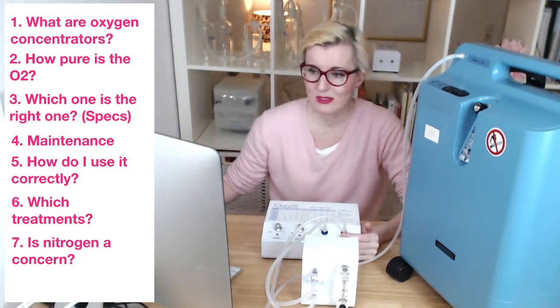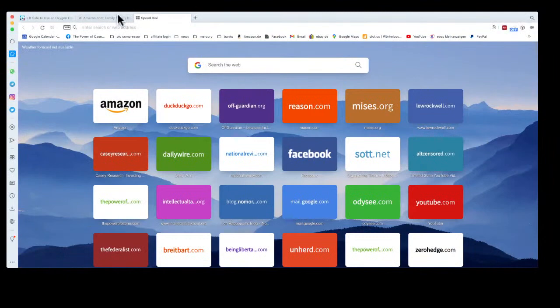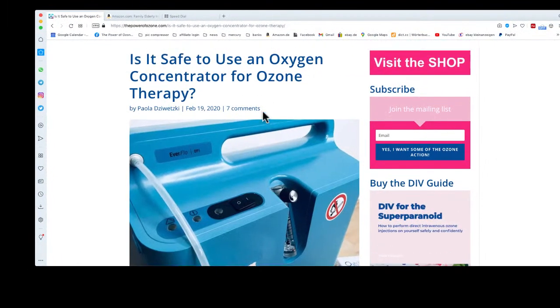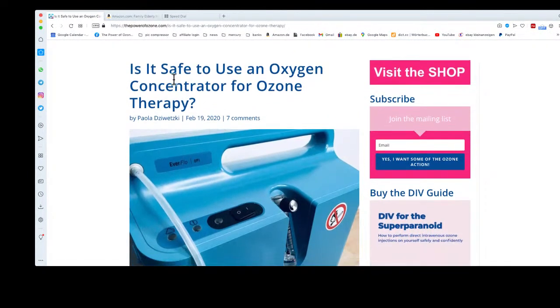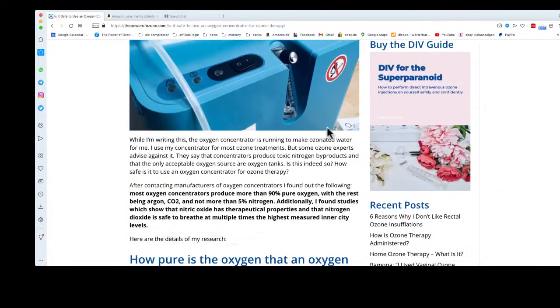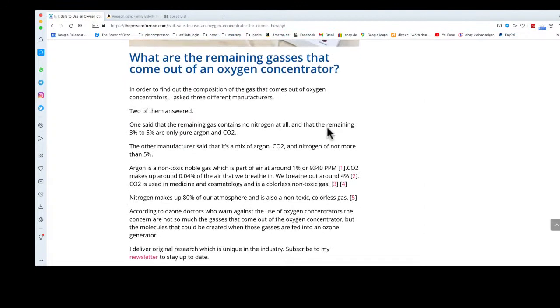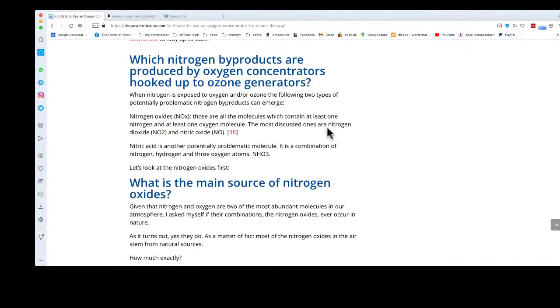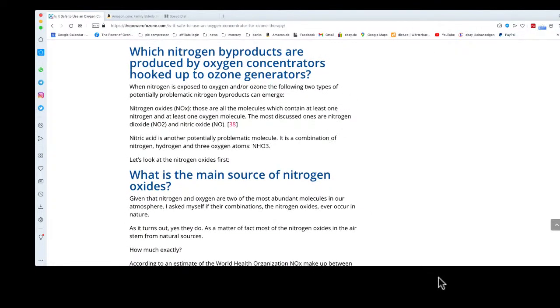So I actually looked into this because I wanted to find out, number one, is it really possible that nitrogen oxides are produced during ozone therapy with oxygen concentrators, and number two, how dangerous are those? And what I found out really surprised me. Well, on one side it did surprise me, on the other side it kind of did not. Now let me switch over to the article I wrote on the subject last year: Is it safe to use an oxygen concentrator for ozone therapy? I looked into studies which dealt with nitrogen oxide and nitrogen dioxide.